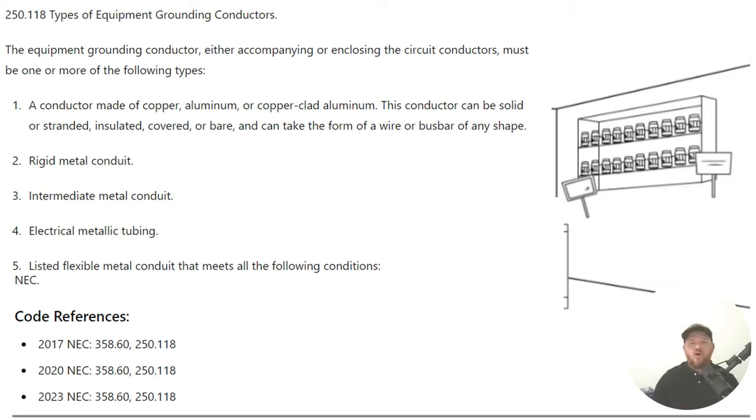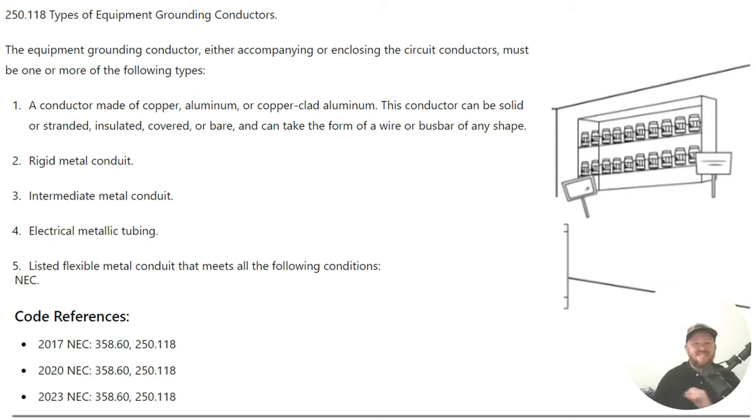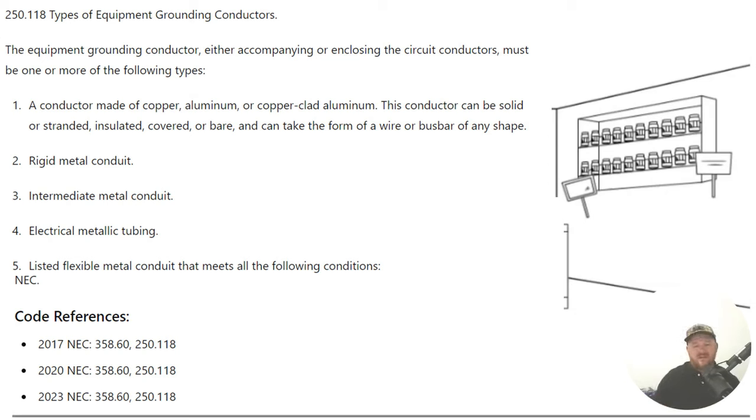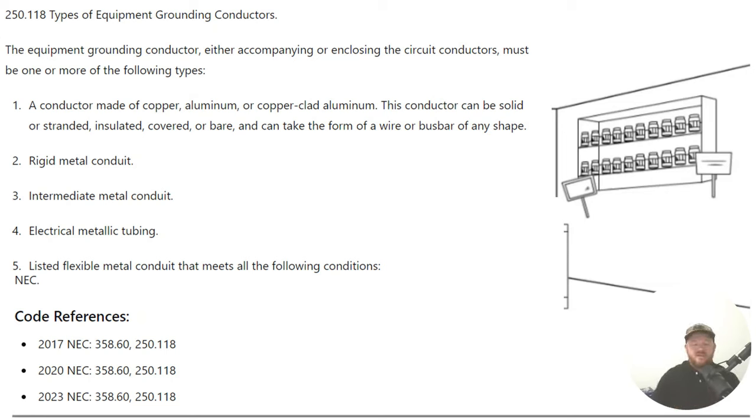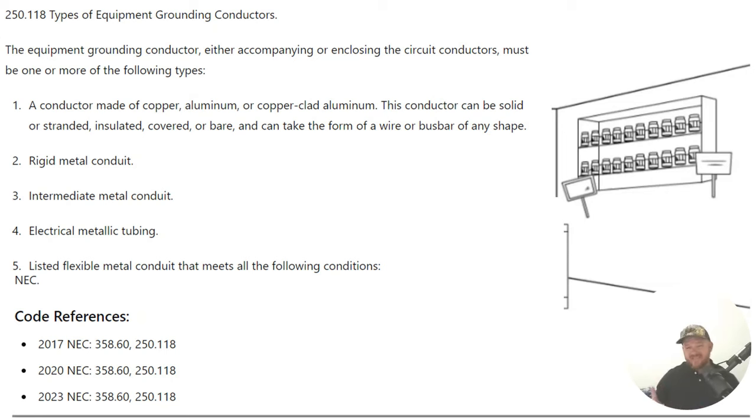So you are allowed to use EMT as an equipment grounding conductor itself. Now, often types, I'm all about pulling a wire type equipment grounding conductor on top of my EMT. I like to do both just for many reasons, in my opinion. And don't forget that there are specific cases in the NEC where you must pull a wire type equipment grounding conductor. I think there are some rules in HVAC in certain scenarios that you must have a wire type equipment grounding conductor. There are other pieces of equipment in the NEC that require or just the manufacturer specs that require a wire type equipment grounding conductor. I'm not going to get in the business of doing a lot of using rigid metal or EMT as my equipment grounding conductor, although if done safely and properly, there's absolutely nothing wrong with it.